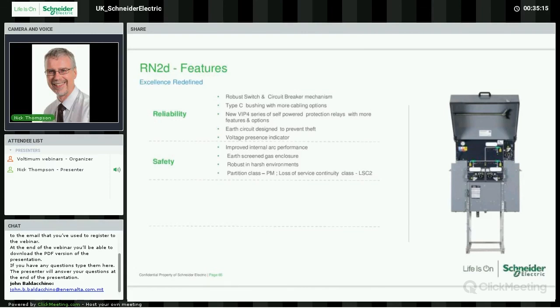Safety: it's fully internal arc tested for both the gas enclosure and the ring switch cable boxes, with blast points at the back of the cable boxes on the ring switches. We're maintaining the earth screen throughout on the gas enclosure, and when you're using an earth screen separable connector with earth screened cables, you now get a fully earth screened system.